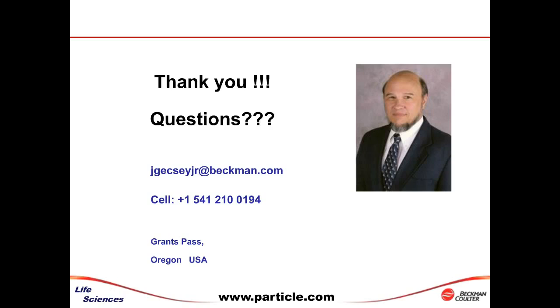And generally, again, you would use a calibration methodology. We don't have something that emulates proteins perfectly today. Again, there are national bodies working on that. But at the moment, we have somewhat of a surrogate in the type of either polystyrene beads or glass beads to represent a spherical object. Unfortunately, most proteins aren't spherical. So I'm not sure exactly in the question what accuracy is going for, but I'm thinking probably we're talking count, and we do have count standards based on spherical material.